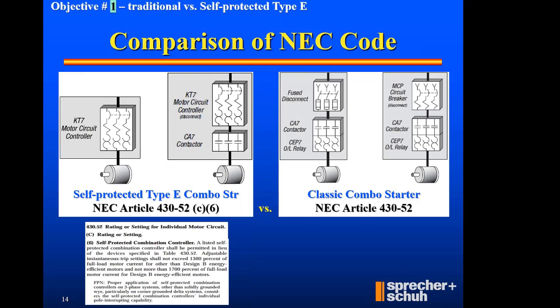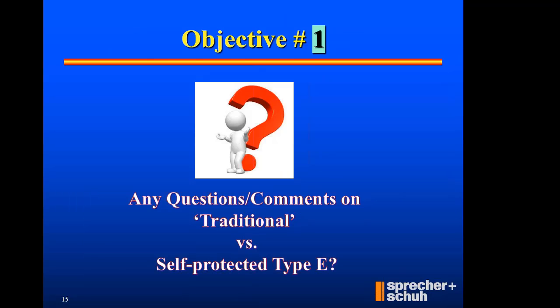However, Article 430-52(C)(6), as in getting the nuts and bolts of 430-52, provides you an alternative of applying the rule of self-protected combination controller. Visually, on the left side, I've got a KT7 only. I've got a means of disconnect, a magnetic armature on the inside, and an overload relay symbol here. As opposed to the same device, if I want to send it a remote signal, I'm adding a CA7 contactor so I can send a signal to energize the coil of the contactor. So we're using the C6 rules: C saying I've got a rating or setting, 6 as in self-protected combination controller. And there's the verbiage from the actual NEC down there at the bottom saying how a controller is compliant. So that's the actual code for self-protected Type E.